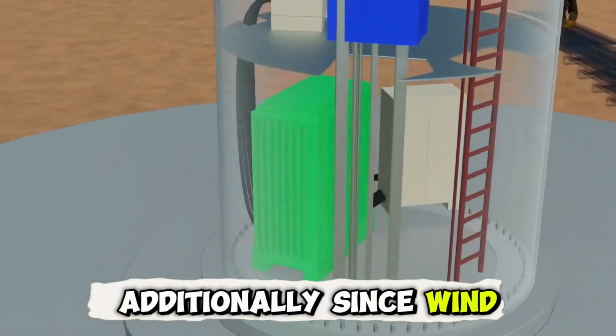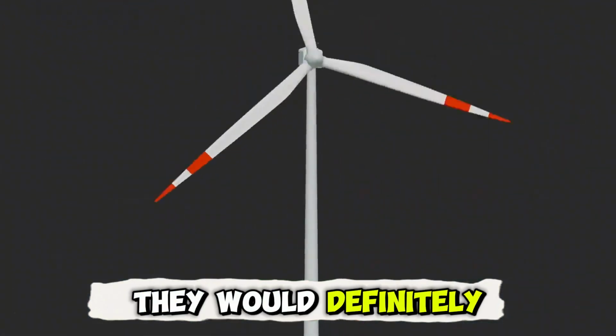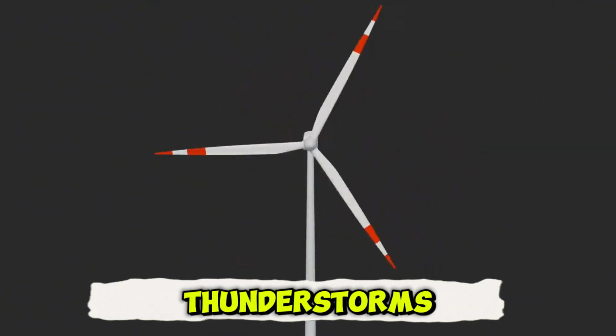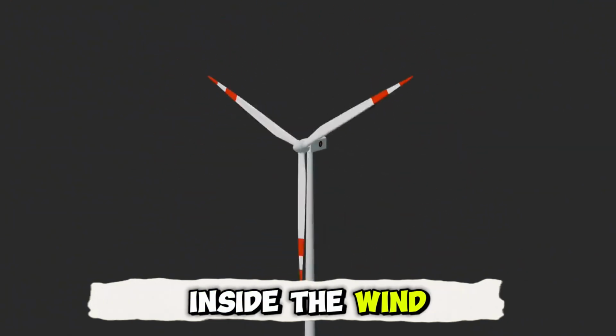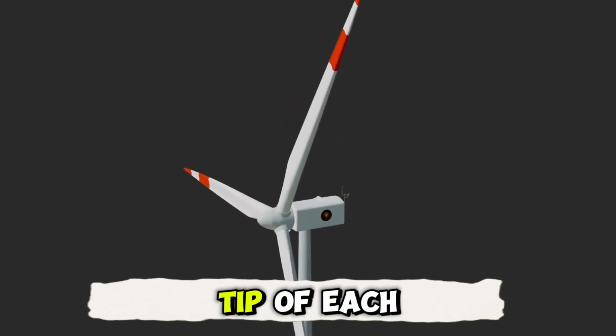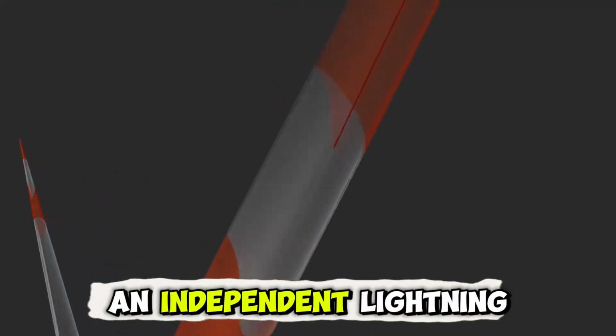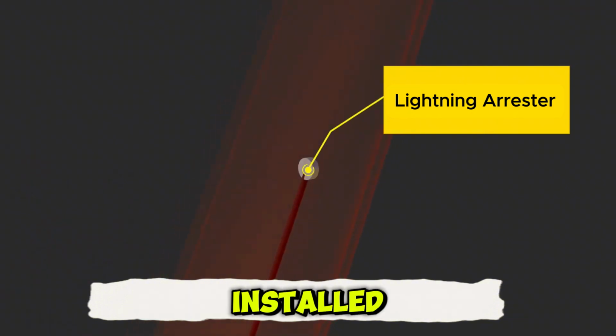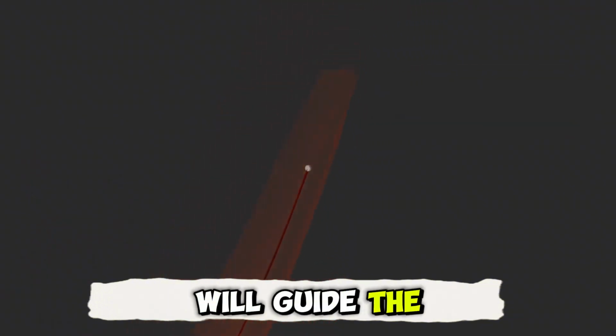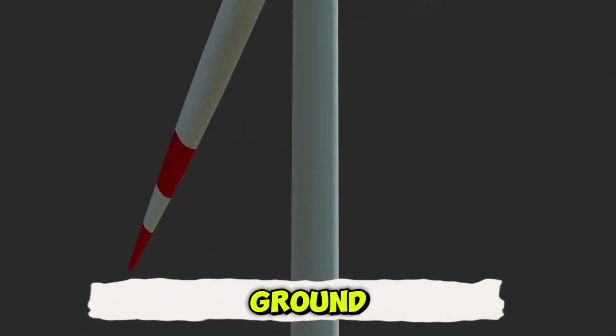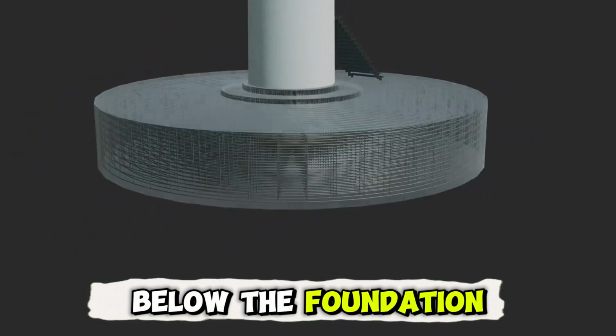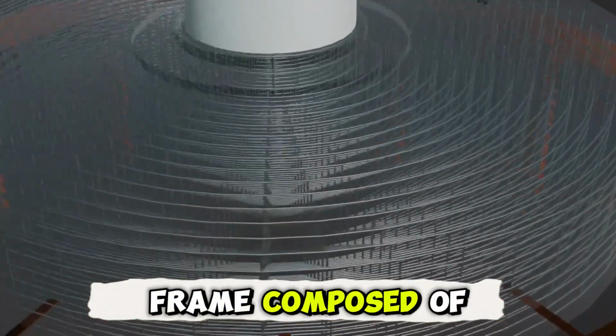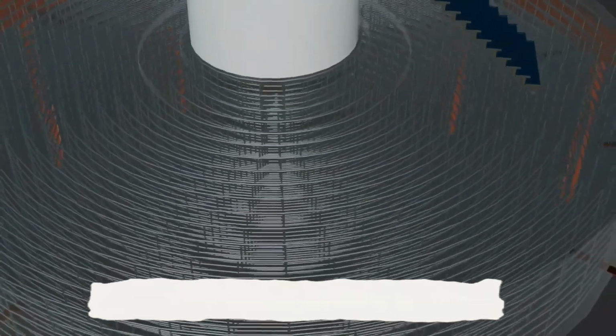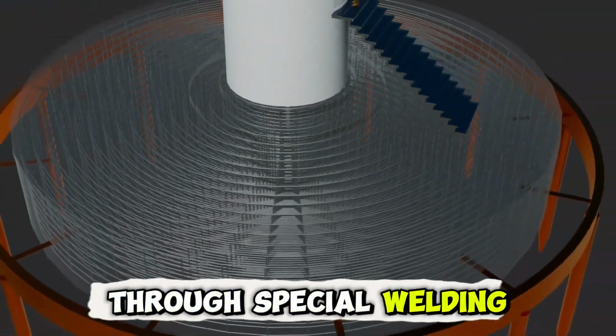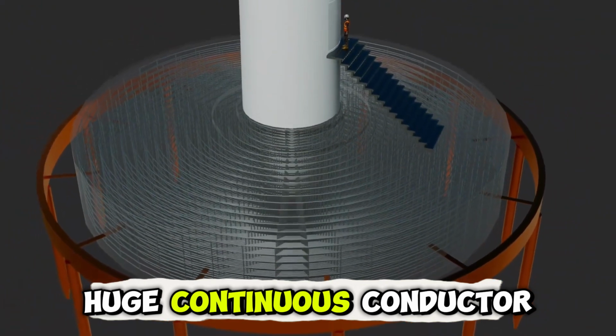Additionally, since wind turbines are so high, they would definitely be struck by thunderstorms, damaging the electronic equipment inside the wind turbine. Therefore, at the tip of each blade, an independent lightning arrestor is actually installed. The lightning arrestor will guide the current all the way down into the ground below the foundation. Below the foundation is a steel frame composed of reinforced concrete. The steel frame, through special welding, can become a huge continuous conductor.